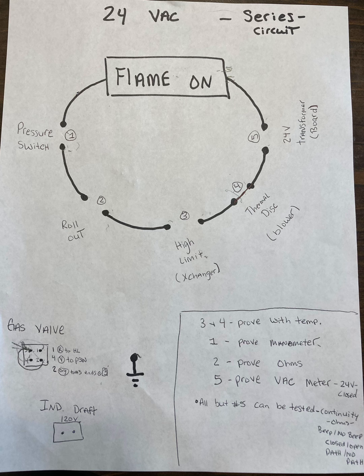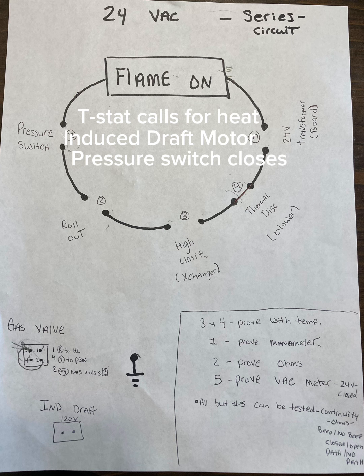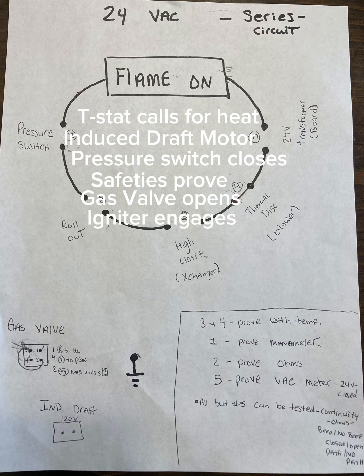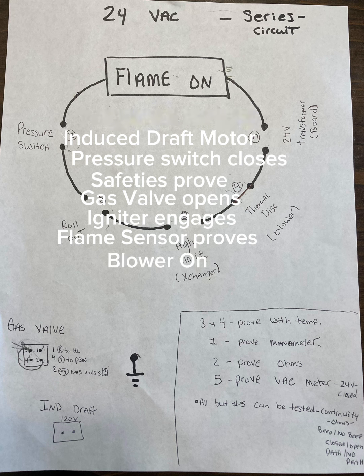One of the things that I really love about a good furnace is it follows steps, it follows rules, and as a good tech, we can know our steps, and we can even break them down into our own understanding so that you're paying attention. Step one, you're running sequence, so the thermostat calls for the heat. Then the induced draft motor turns on, the pressure switch is closed, the safeties prove themselves to be closed, then the gas valves open, then the igniter ignites, then the flame sensor proves it's got flame, and then the blower turns on. So it never changes these steps.